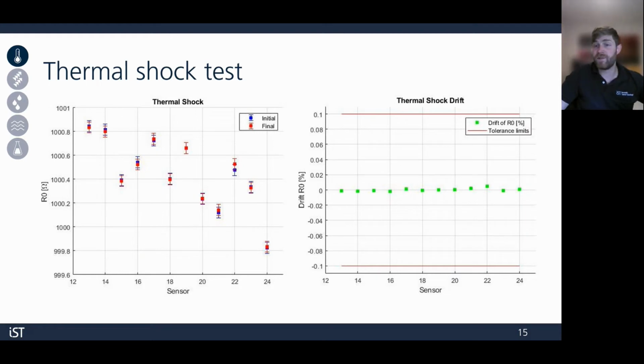Next up, we have a test for drift after thermal shock. In this case, the sensors are repeatedly transferred between negative 65 Celsius and plus 200 Celsius. Measurements are taken before and after, and as we show here on the right, there's barely any drift observed for all the different sensors that we've tested.